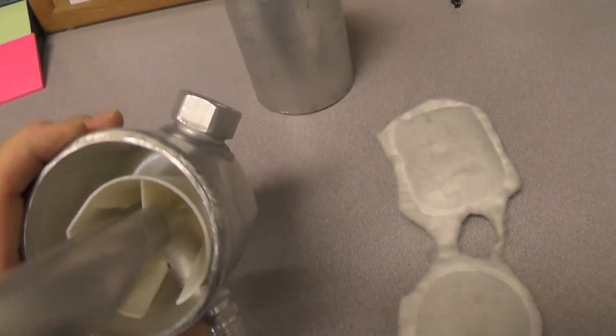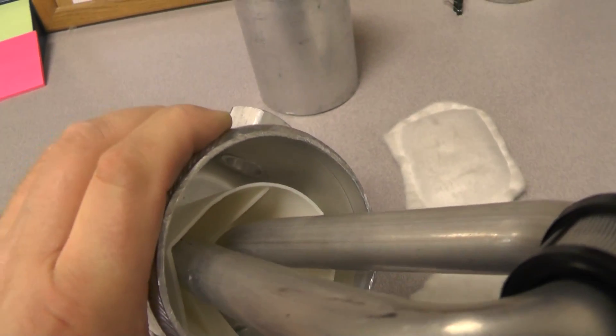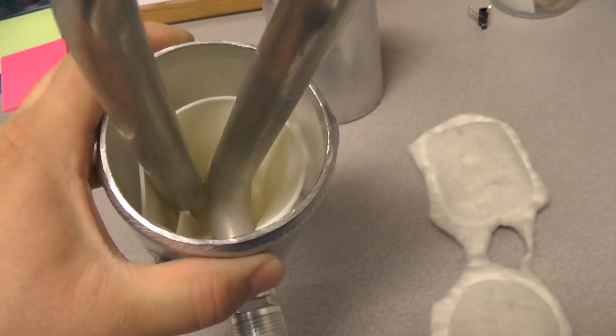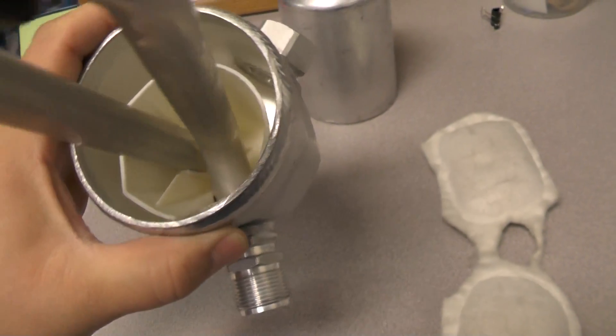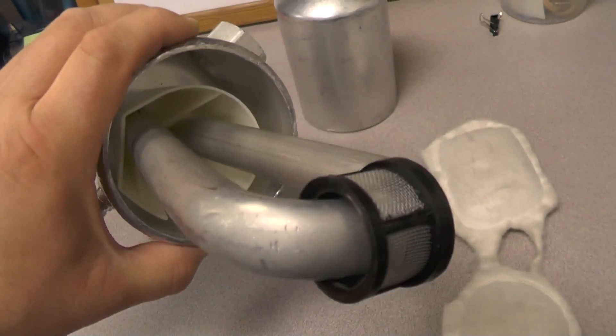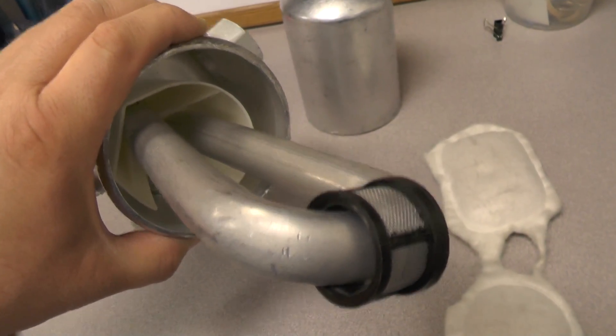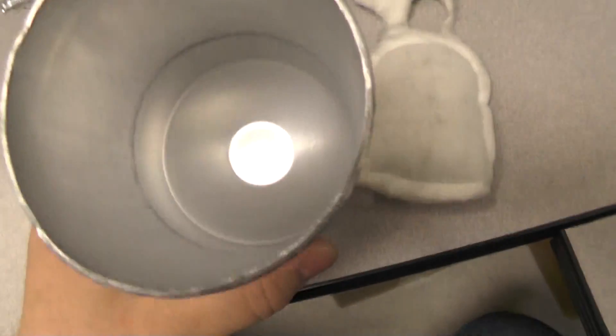And then up inside here, so that's the input port. And you see there, it's just a hole into the top of the can. And then there's this white plastic baffle plate. So when the refrigerant comes in, it'll hit that baffle plate and then fall down. And it'll get into the bottom of the can here, right?